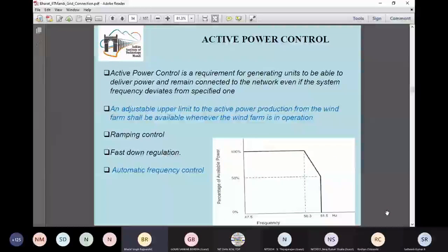We are also aware, as electrical engineers, that in our power system, whenever the generation is more and the load is less, the frequency of the system increases. Our nominal frequency is 50 hertz with a specified band. In this diagram, you can see that whenever the frequency of a system is increasing, it is expected that the generation should be reduced or the load demand should be increased. So it is expected that once 50.3 hertz is crossed, the generation should be reduced. If an adjustable upper limit is available with the operator, then this exercise can be done. And beyond 51.5, it is expected that the generation should be back down to the zero level. So this is the understanding of active power control.